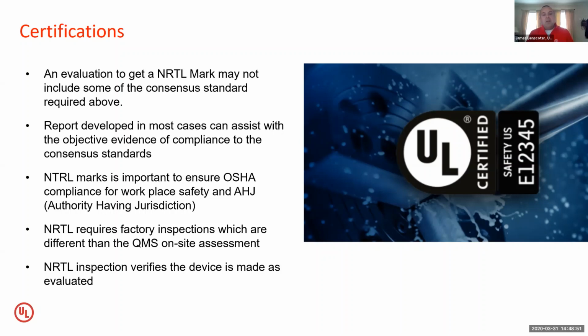The marks really come into play when we talk about workplace safety compliance from an OSHA perspective. A lot of hospitals will have different regulatory requirements of what they will accept on devices. Also, it is important for authorities having jurisdiction if your device is of such nature that it is permanently installed. The NRTL mark does require verification that the device is built as described and tested. So you kind of think of that as a mini audit, and it does occur on site. But it is different than the quality management system, which would be a separate activity. So with that, we can go to the next slide, please.